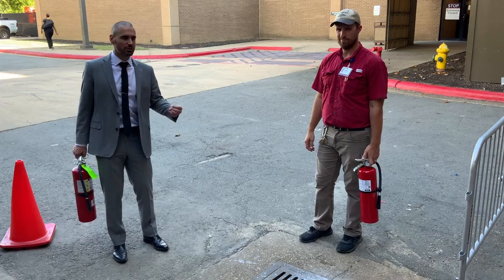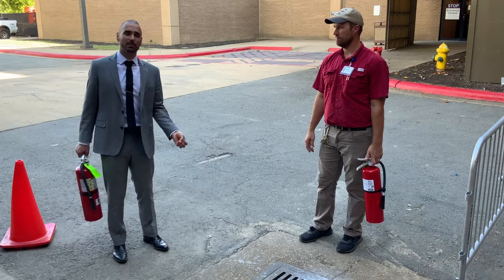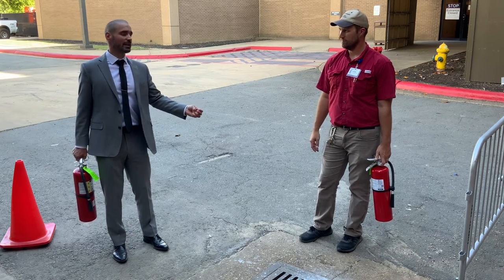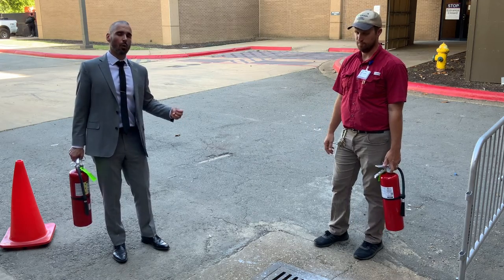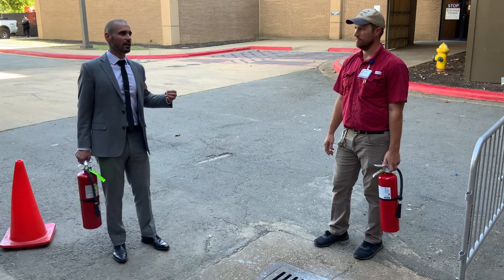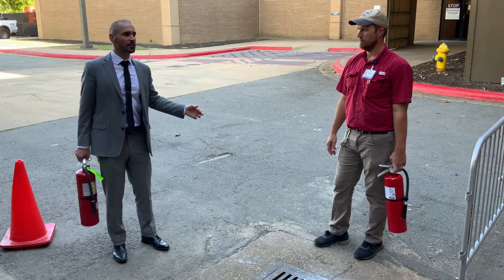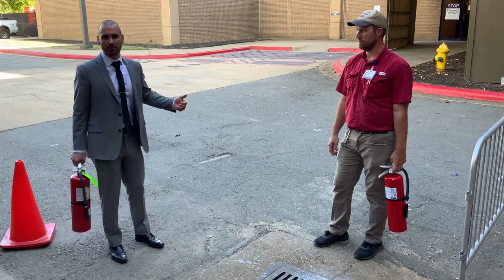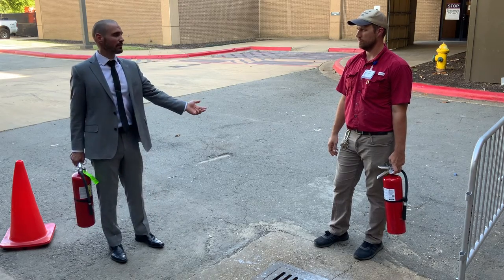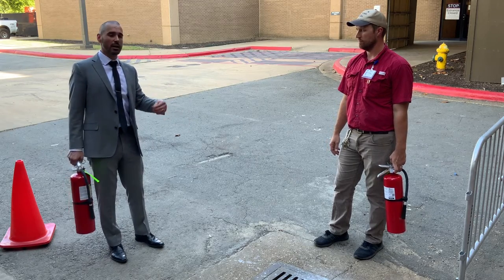Placement of extinguishers, type of extinguisher, and size of extinguisher vary based on occupancy and what's required. For example, for an OR, you have to have a clean agent type extinguisher. For helipads, you have to have a certain size of extinguisher, typically foam, based on the size of your helicopter. In hospital kitchens, of course, you have to have K extinguishers. All different kinds.